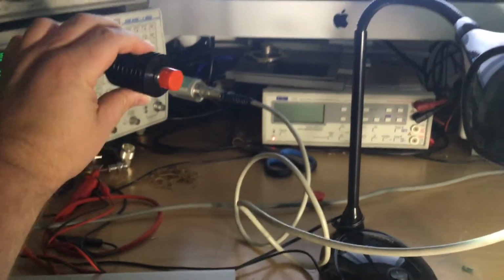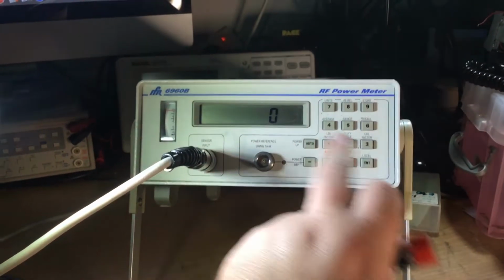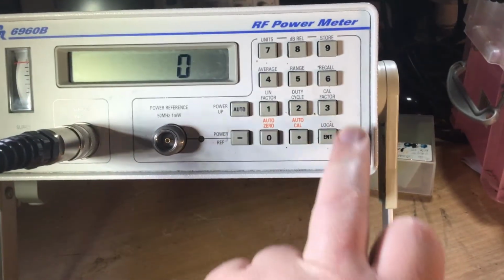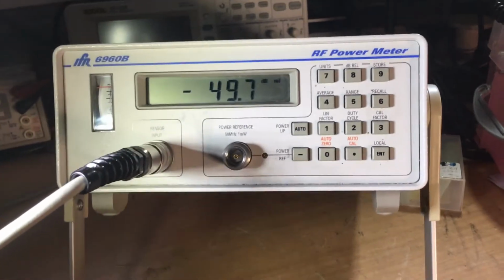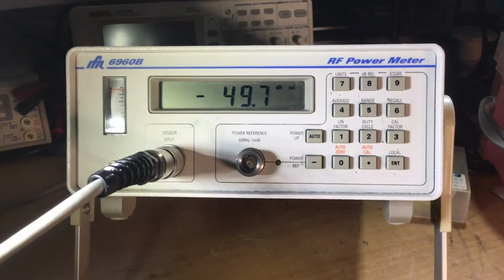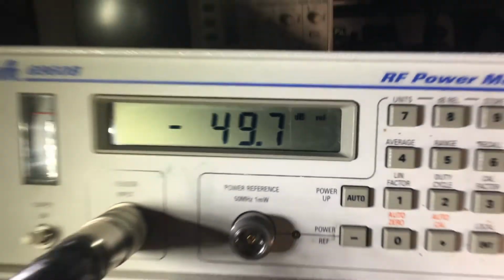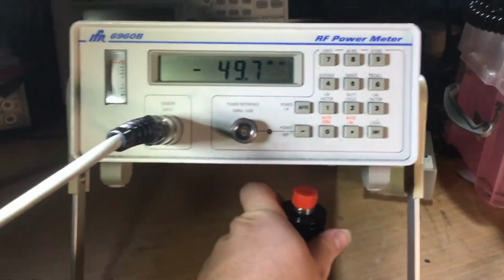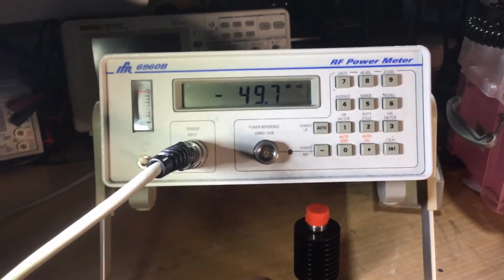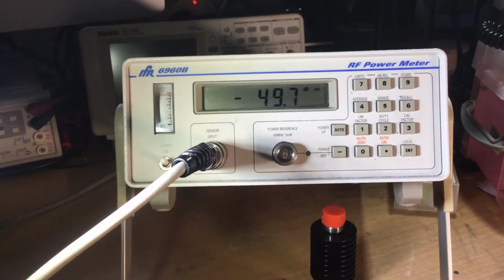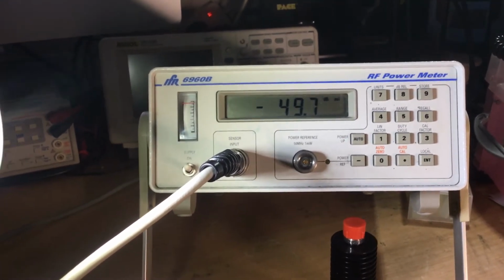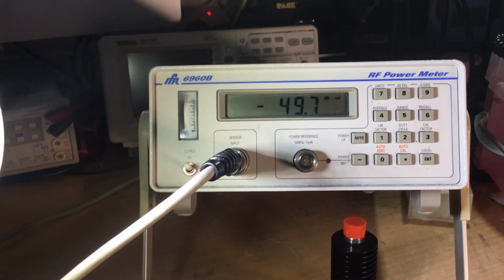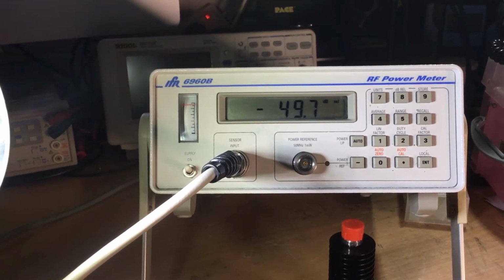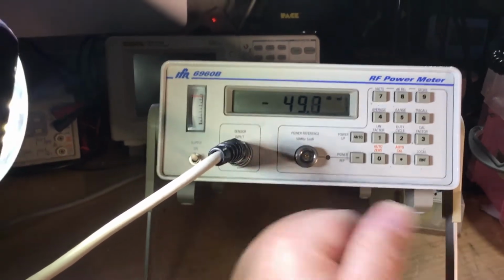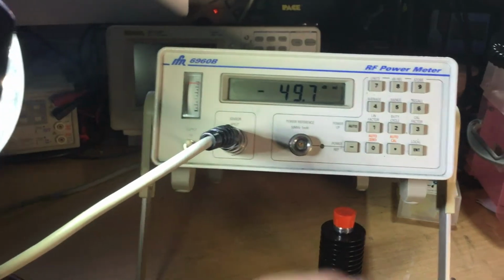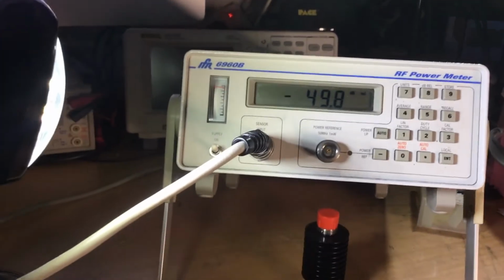But if I was to attach this 30 dB attenuator in, we'd change that level to 30 dB, enter 30 there and press enter, and then it would take that power level into account. So that's where that is quite useful in this application. It says positive relative values to account for amplifier gains can also be entered. The dB offset linearity facility may be used with linear units so that the transmitter output powers can be displayed in watts. So that's how you turn this microwatt meter capability into watts, by using external attenuators on the sensor.